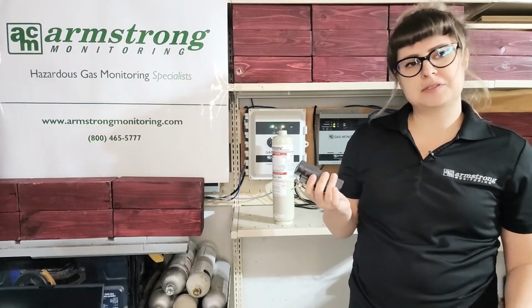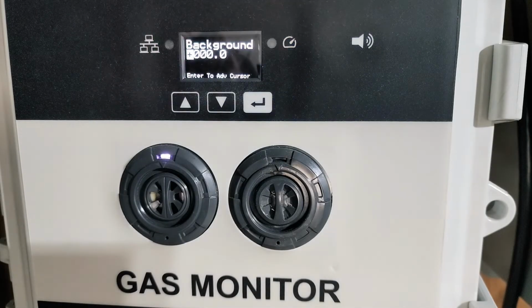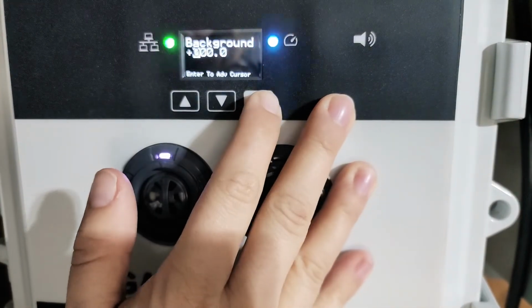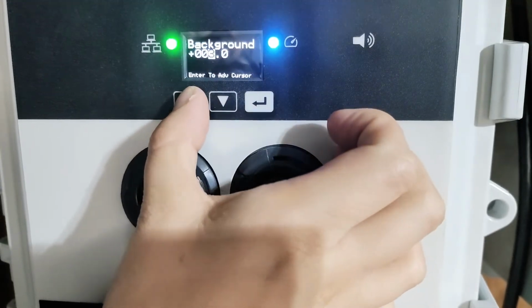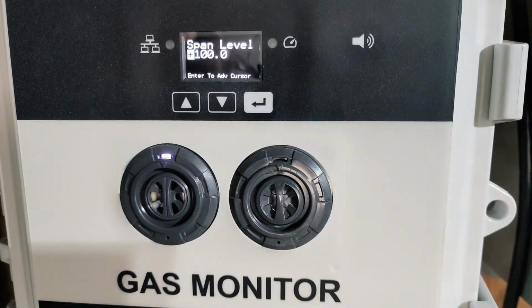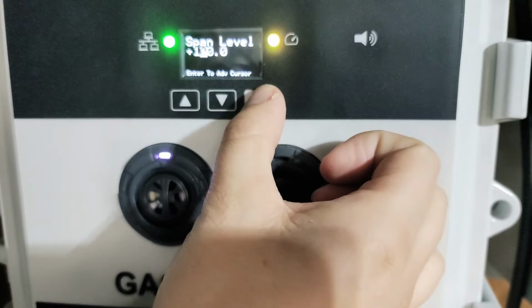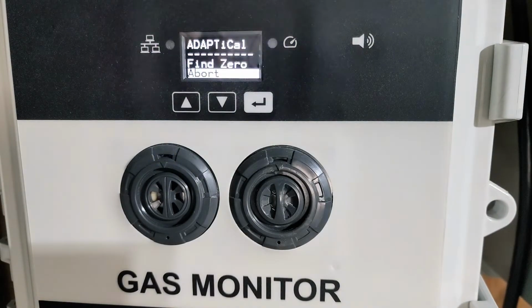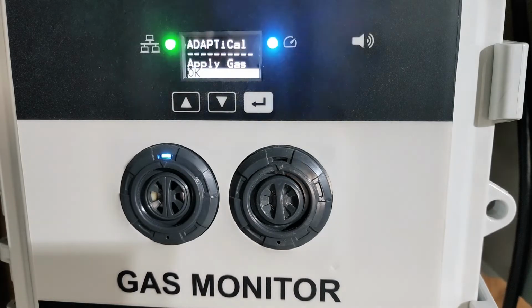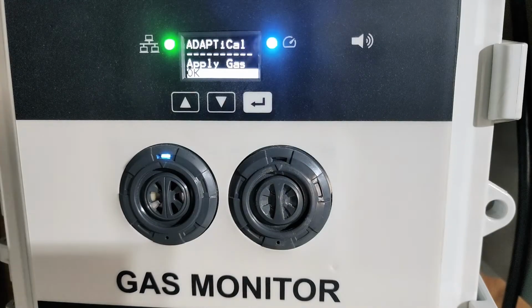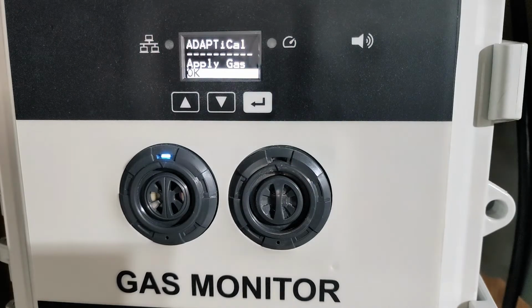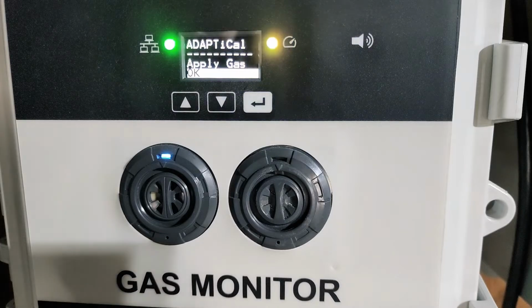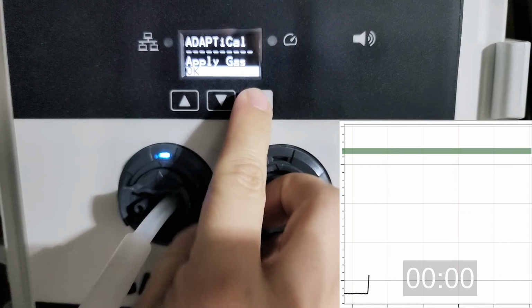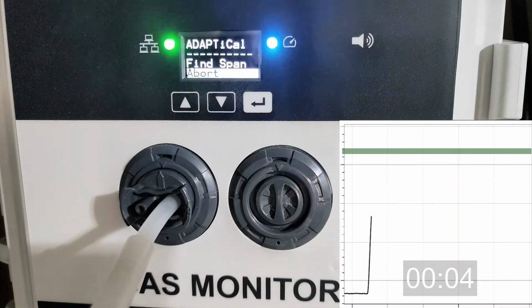For the second option, use the recently calibrated portable to measure the background carbon monoxide in your environment. For example, here, we're getting a reading on our portable of about 5 ppm. I will then enter 5 as my background. Next, it asks for the span level, which is 100 as described previously. It will enter buffering, and then it will find zero using the ambient air, where you'll be prompted to apply gas. Here you can open your calibration gas cylinder. Apply the calibration adapter. Select OK. It will find gas and then enter the find span phase.